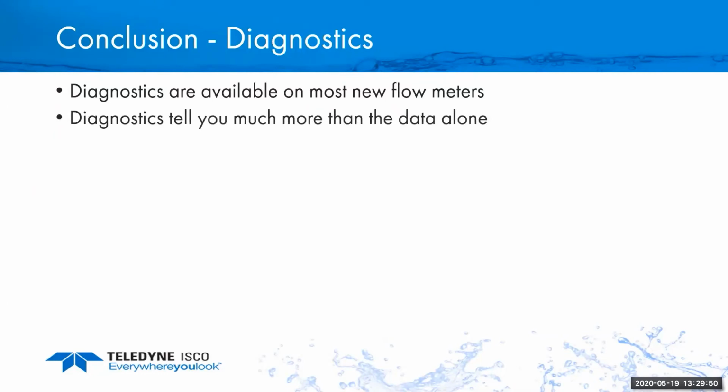We will get graphs that people will send us something from a SCADA system. That means nothing to us. Yep, this did this, it flatlined. We can't tell you anything from that data. We really need this diagnostic information. So whether it's product support or application guys or whatever, we need to know what that meter saw, much more than just the pretty graph alone.